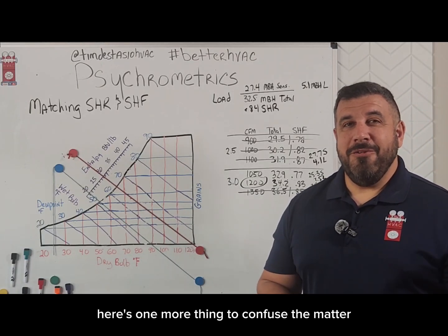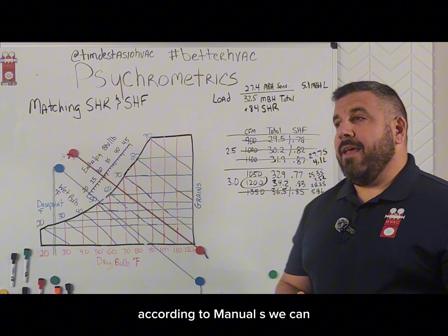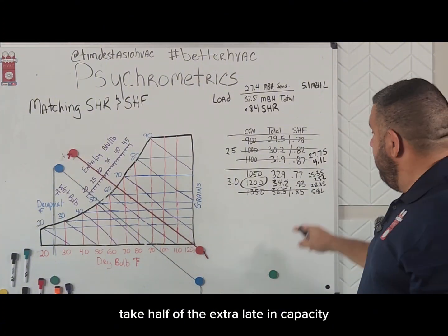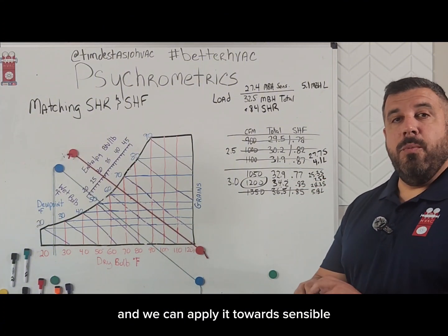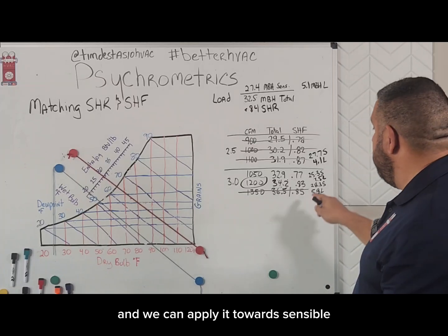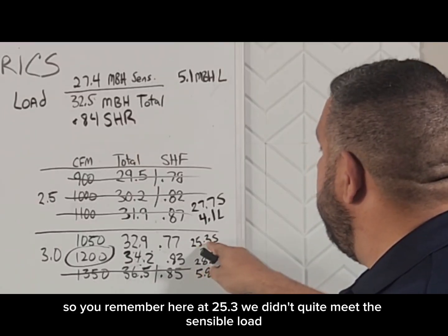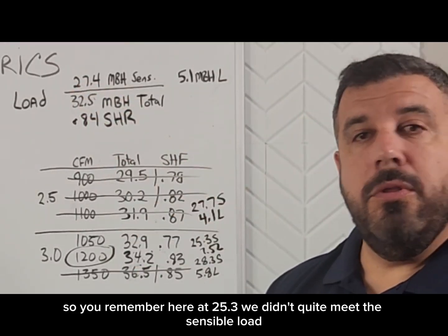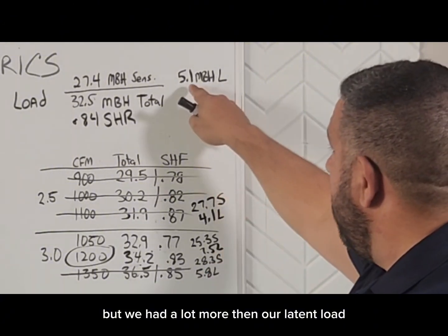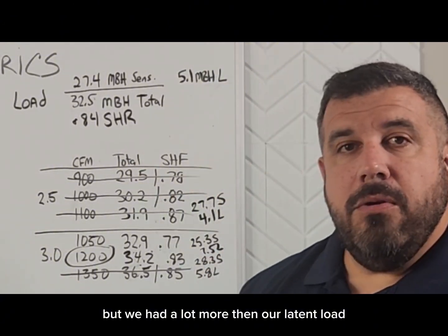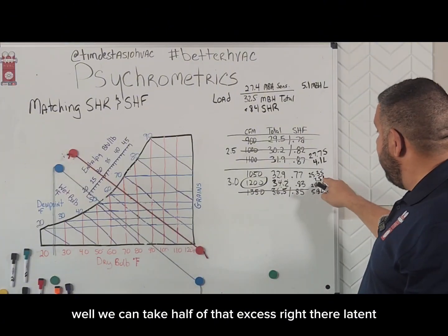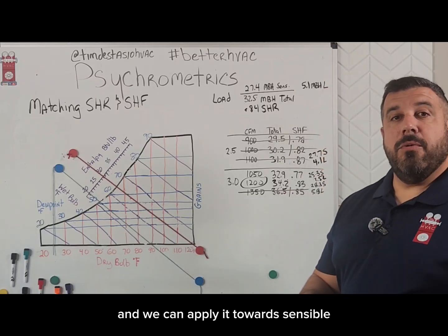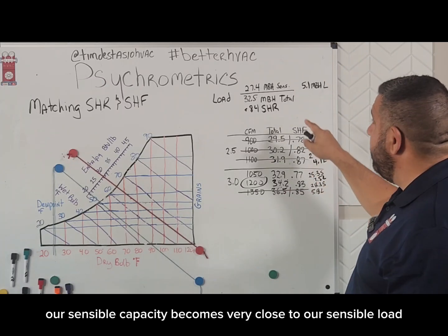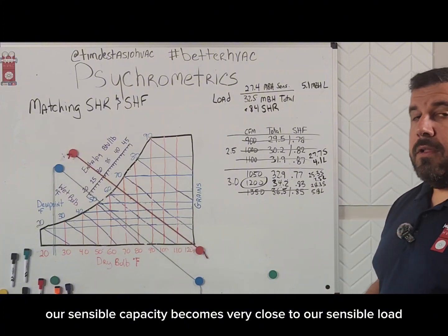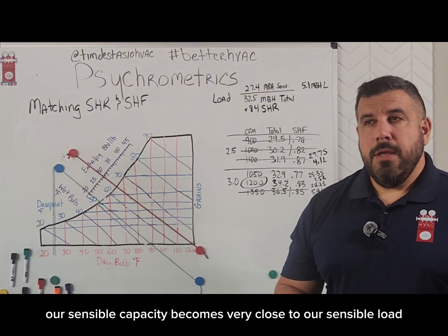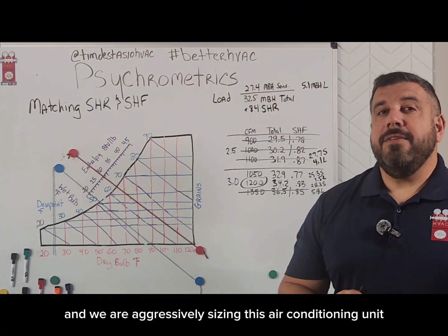Here's one more thing to confuse the matter. According to Manual S, we can take half of the extra latent capacity and apply it towards sensible. You remember here at 25.3, we didn't quite meet the sensible load, but we had a lot more than our latent load. Well, we can take half of that excess latent and apply it towards sensible, and all of a sudden our sensible capacity becomes very close to our sensible load, and we are aggressively sizing this air conditioning unit.